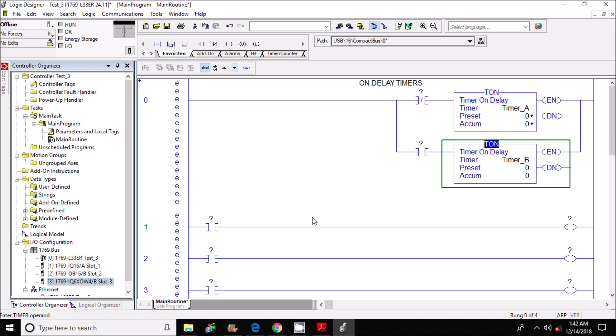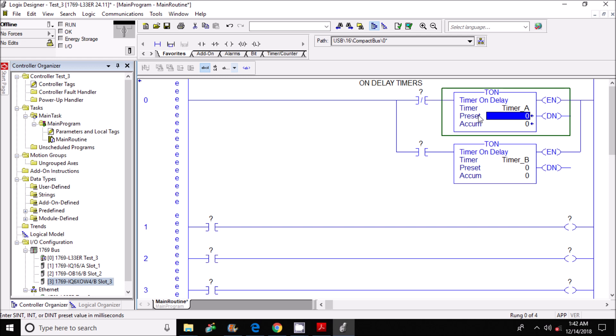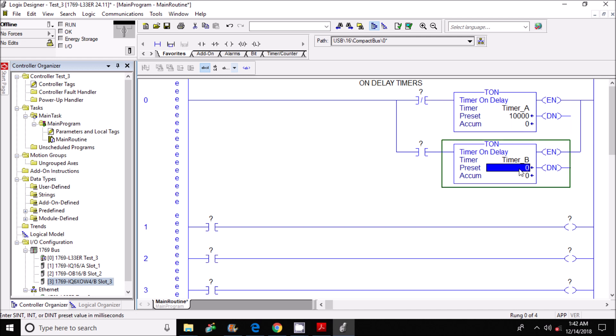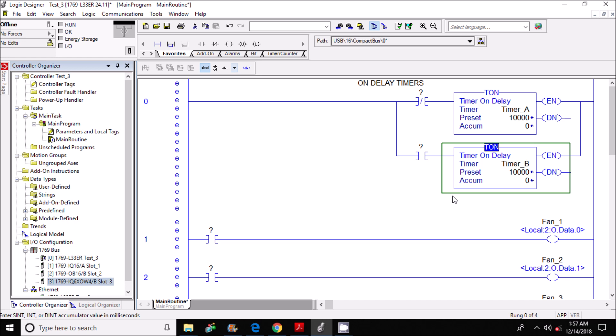Next what I need to do is give these timers a preset value. So I'm going to come up here to the top timer, timer_a, and click the preset area. Now these timers are in milliseconds, so if I want a timer for 10 seconds I have to type in 10, then add three zeros behind it and that will give me my 10 seconds, and then click enter. And do the same thing for timer_B: type in 10,000, gives me 10 seconds, click enter and I'm done.